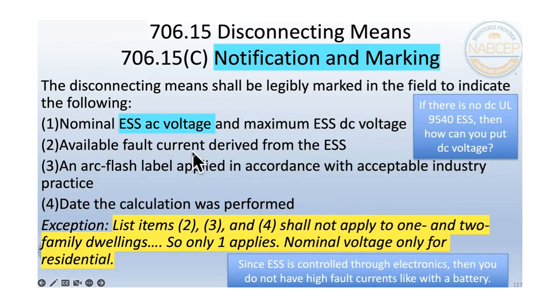So this one too, the notifications and markings. I know that's something that you're interested in, is the markings. And you go through this big long list, and then it says if you're doing residential 1 and 2 family dwellings, you only have to do number 1. So number 1 is the AC voltage. And a lot of times you don't even have DC voltage. You could say perhaps that you do between the battery and the inverter. You might as well mark that there.